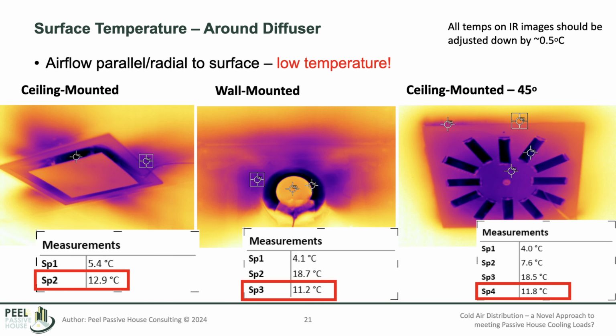In terms of surface temperature, basically if you have a diffuser that pushes air out radially or in parallel to the surface of the diffuser, you're going to get cold temperature - kind of obvious, but now we have testing to show this. Whether it's ceiling mounted or wall mounted, if it's parallel, it's going to condense.